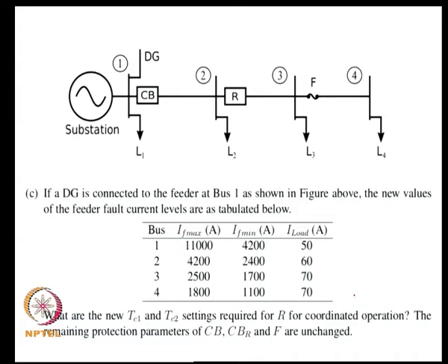The next problem involves a DG that is connected. Because of the connection of the DG close to the substation at the very upstream, the fault current levels across the feeder go up. This is a simpler possible configuration; we could have DG connected elsewhere along the feeder. Because the fault current levels have gone up, you are asked to recalculate Tc1 and Tc2 settings to achieve coordination. We will look specifically at what the concerns are rather than redoing all the calculations.